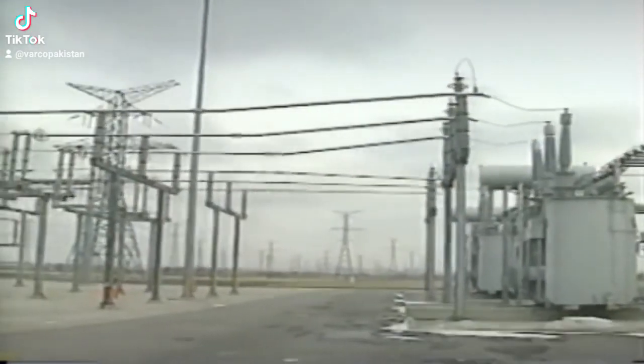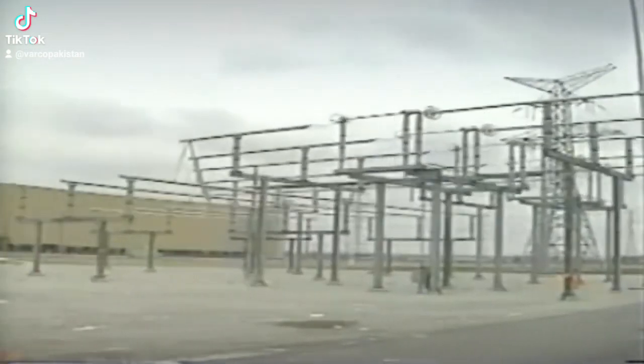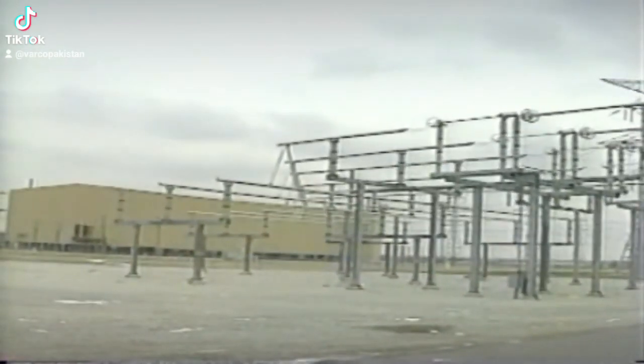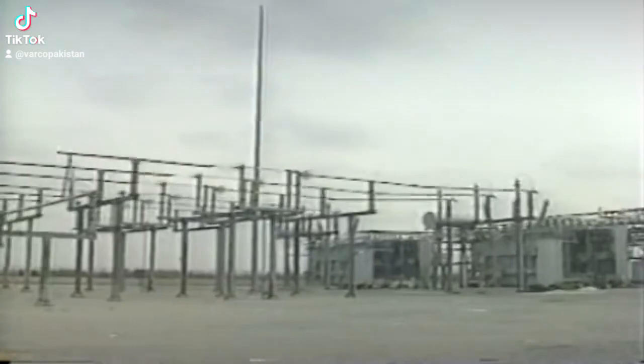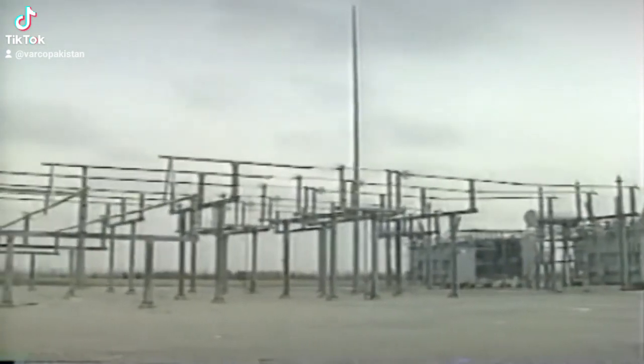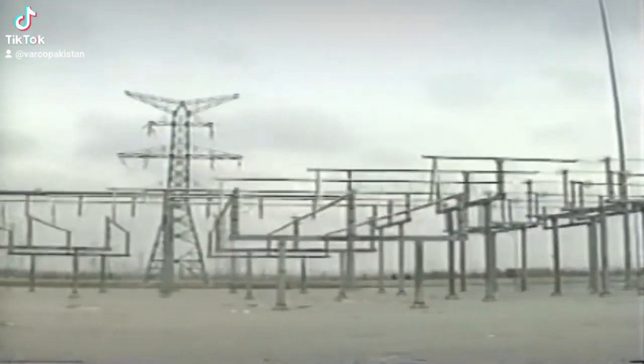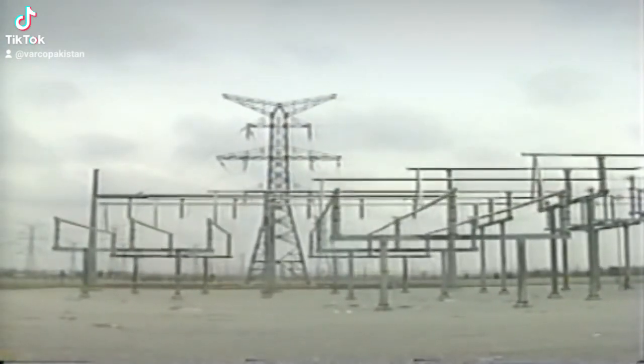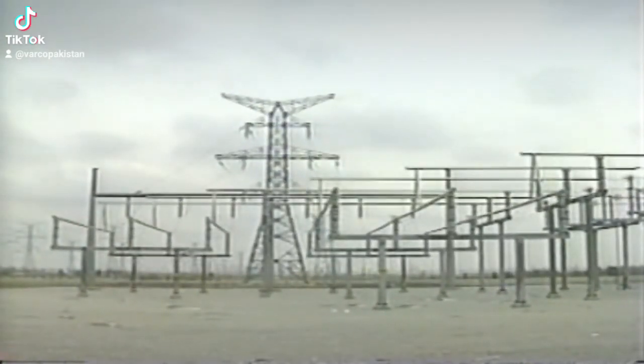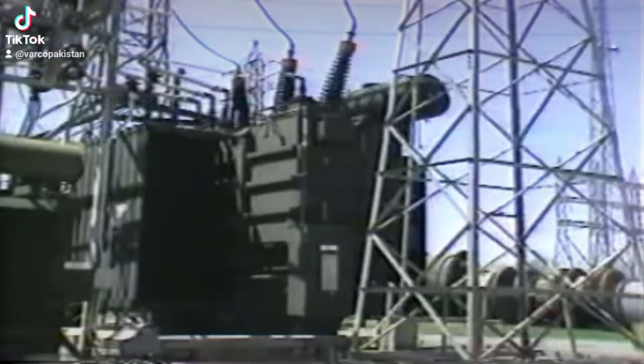Before any primary equipment is connected into the existing power system, the phasing must be proved. In most installations, the primary circuitry is exposed so that a visual inspection can be made to ensure that the primary phasing is correct. That is, to make sure, for example, that the A phase of the bus is connected through the A phase circuit breaker and disconnects to the A phase of the transmission line. Similarly with the B and C phases. However, this visual inspection is not always possible.